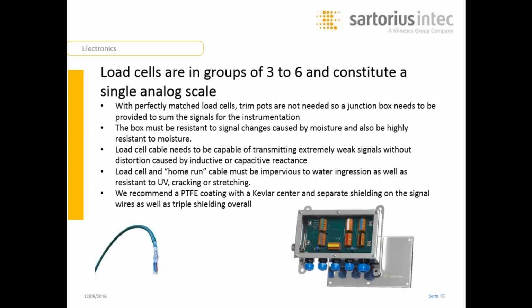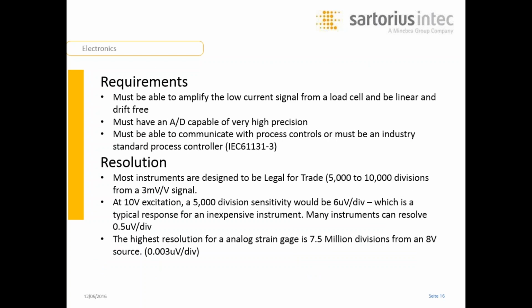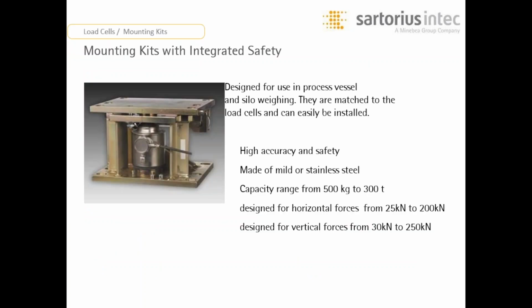Load cell and home run cable must be impervious to water ingression as well as resistant to UV, cracking, or stretching. We recommend a PTFE coating with Kevlar center and separate shielding on the signal wires, as well as a triple shielding overall. This will reduce noise and produce a much cleaner, very small signal back to the instrumentation.